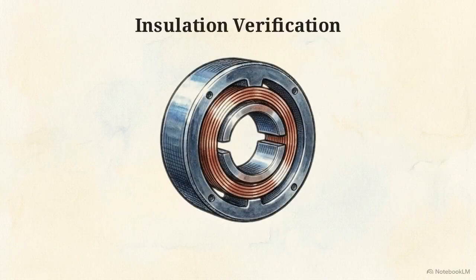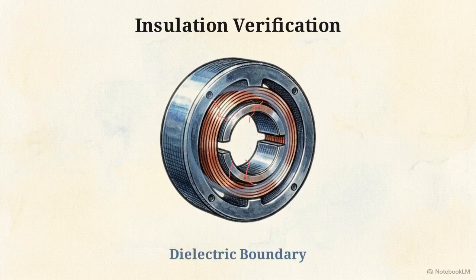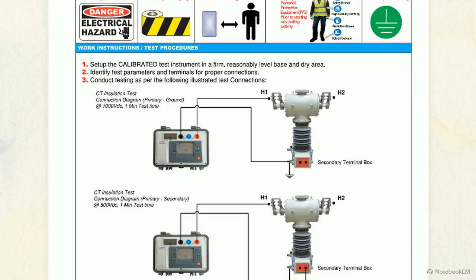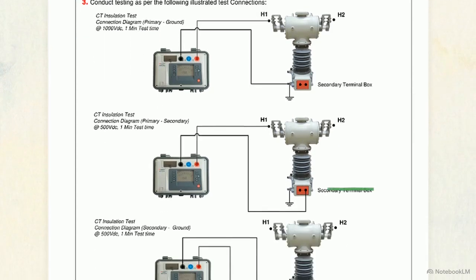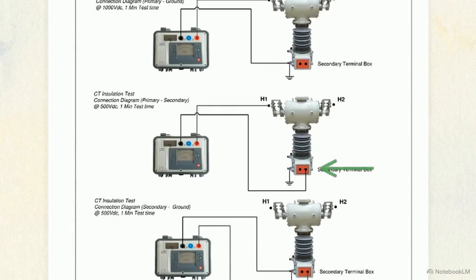The testing sequence begins with insulation verification. This process maps the safe dielectric boundaries of the CT, ensuring no leakage paths exist between the windings and the chassis. The first connection targets the primary to ground boundary. The Megger is connected between the primary terminal H1 and ground, applying 1000 volts of DC for exactly 60 seconds to measure baseline resistance. Next, the leads are shifted to test the primary to secondary boundary.